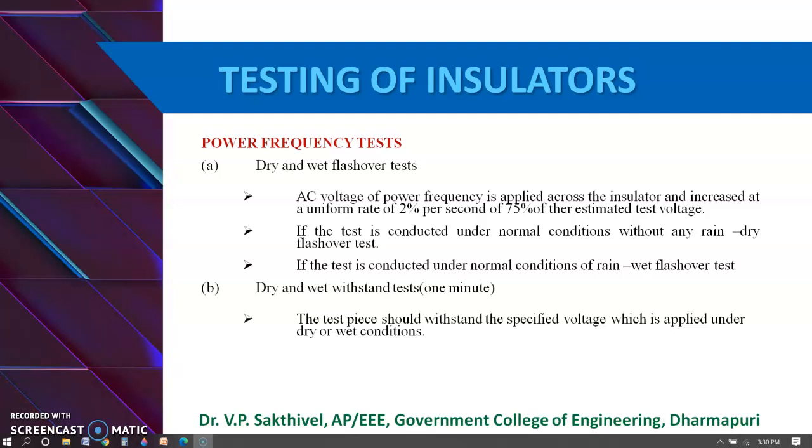For the wet flashover test, we have to spray water at least 1 minute before the voltage application, and the spray is continued during the voltage application.